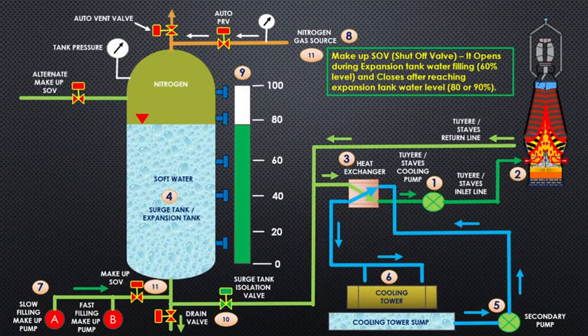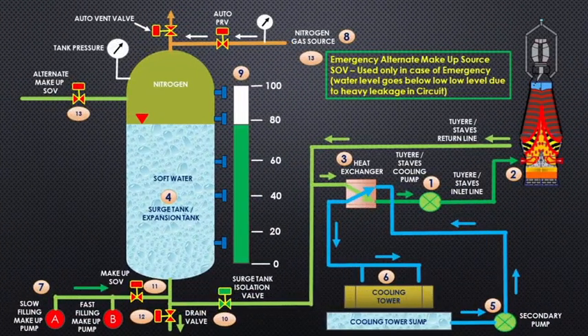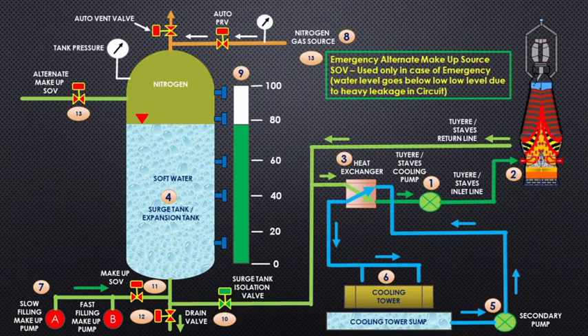Makeup SOV (shut off valve) opens during expansion tank water filling at 60% level and closes after reaching expansion tank water level at 80 or 90%. Emergency or alternate makeup source SOV is used only in case of emergency when water level goes below low low level due to heavy leakage in circuit.